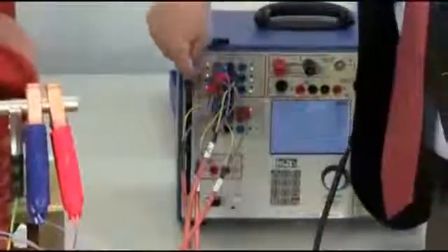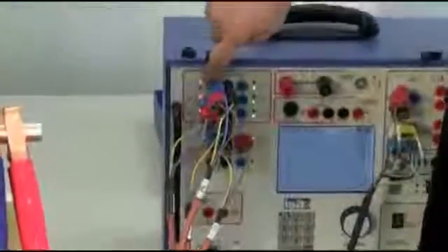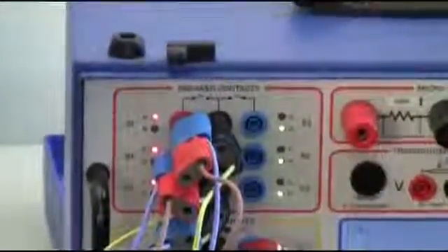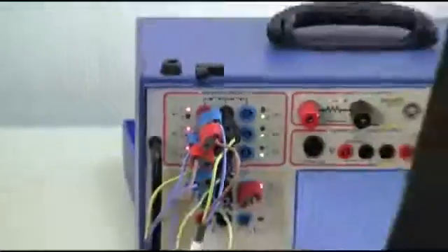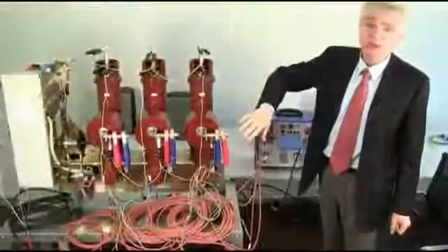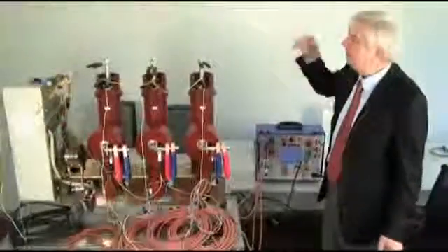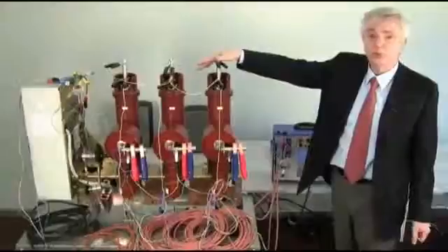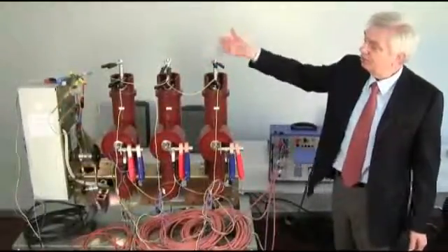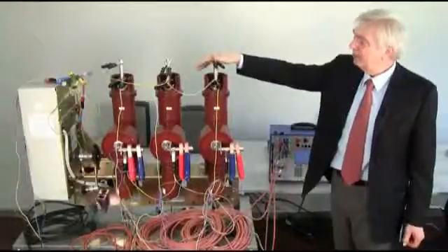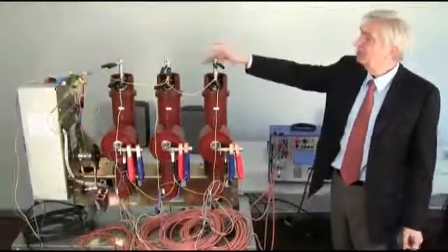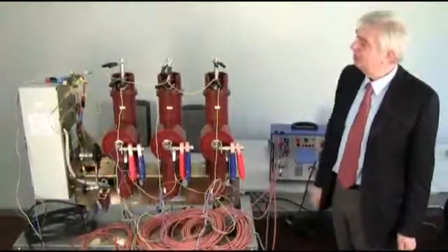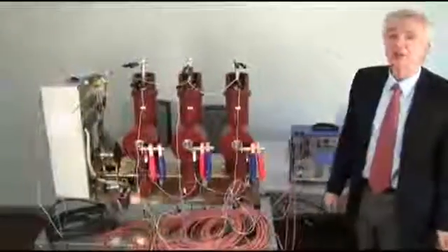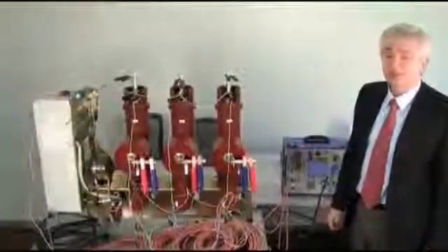It is not easy to be seen, but this one and then the other two LEDs are on, telling me that the circuit breaker is closed. Why is it closed? It should be opened. We have opened it. It is seen closed because I still have the grounding on both sides. So now you are ready to operate, and before starting you have to remove the grounding on one of the two sides of the circuit breaker. About this operation that puts some degree of unsafety on your testing, we will discuss this later on when we discuss the both sides grounded option.